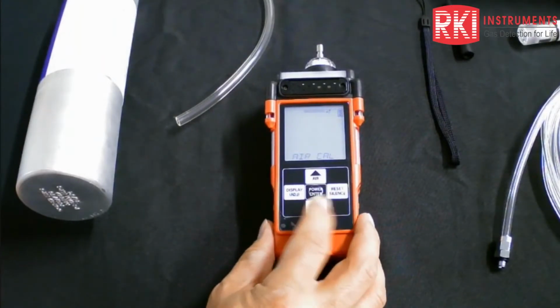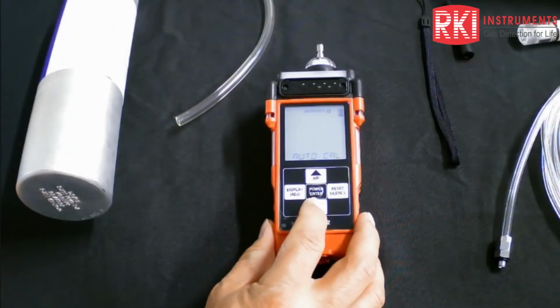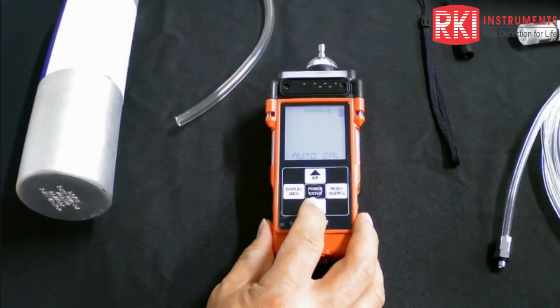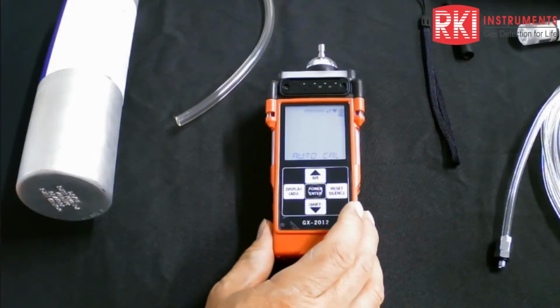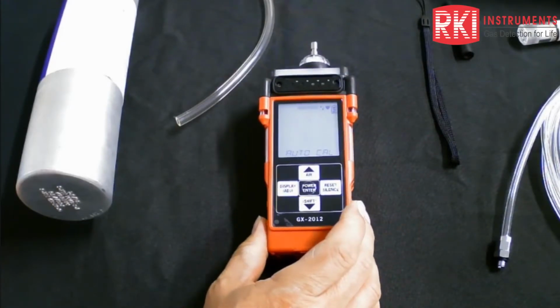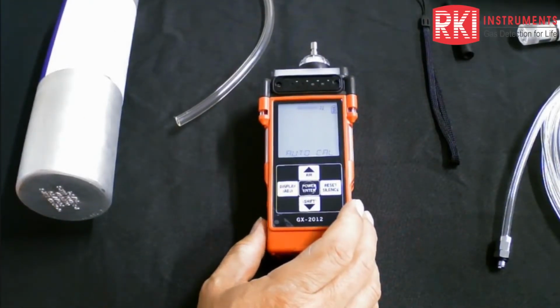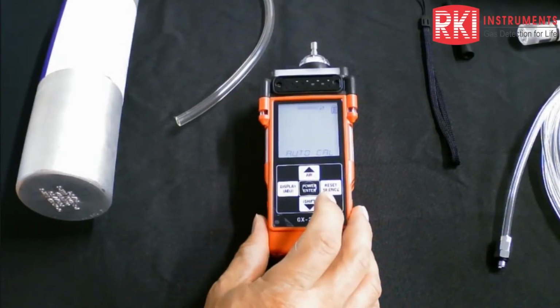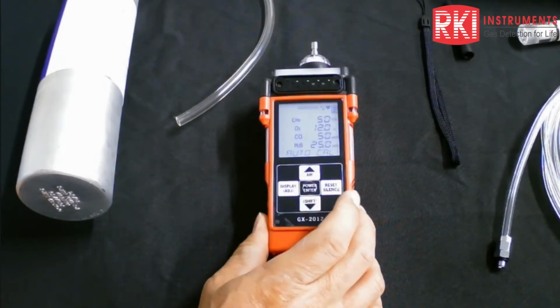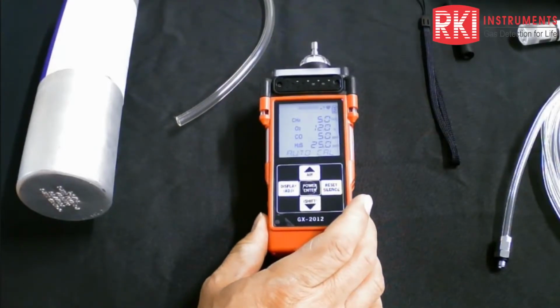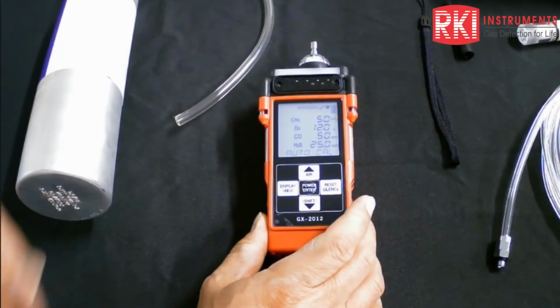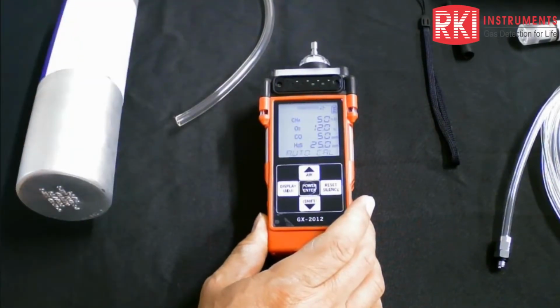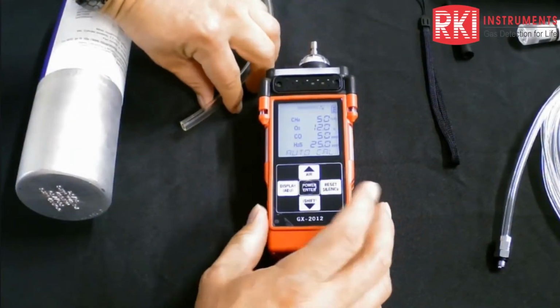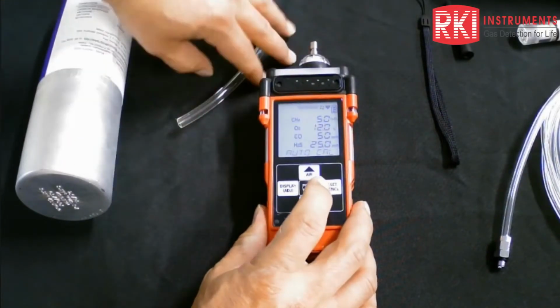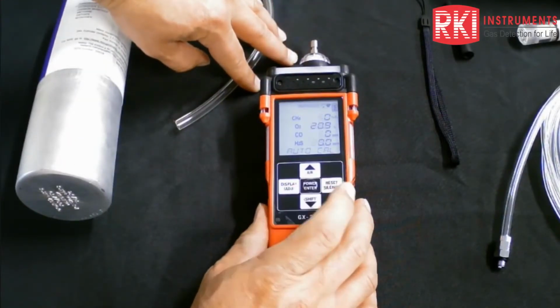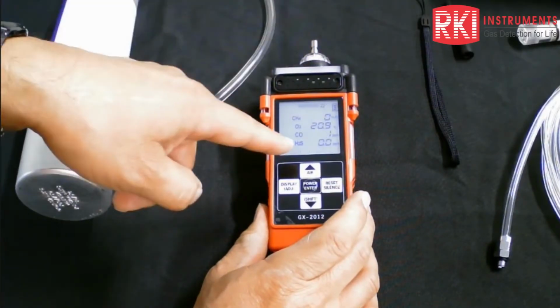Okay, the next thing I want to do is go down to auto cal, and basically we're going to calibrate all 4 sensors at once, and then we'll calibrate that thermal conductivity sensor afterward. Okay, so I've already got my regulator and tubing hooked up to the cylinder, and I'm going to press the enter button here. And right now, I've got my values that the unit expects to see, which do match the cylinder, so that's good. All right, and I just want to continue with that. So I'm going to press the power button. Once the values are valid and verified, press the enter button, and right now it says auto cal is flashing.